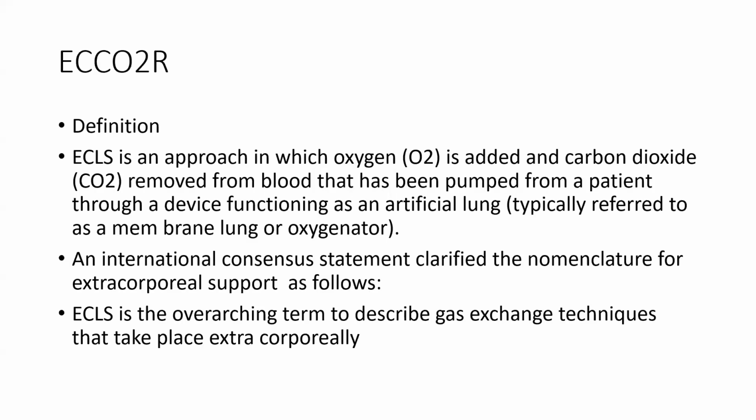So the extracorporeal system is an approach in which oxygen is added and carbon dioxide is removed from the blood that has been pumped from the patient through a device functioning as an artificial lung, typically referred to as a membrane lung or oxygenator. The International Consensus Statement clarified the nomenclature for extracorporeal support as follows.